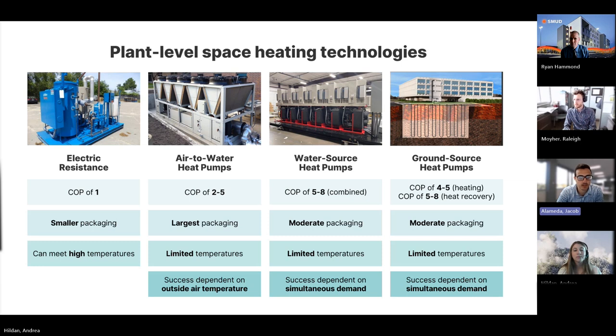The next up on the list are water source heat pumps. These are similar to air source heat pumps, but instead of pulling heat out of the air with the vapor compression cycle, this equipment uses some other water source to pull heat out of. This doesn't necessarily work on every project because you need a water source with enough heat in it to make it work. And your water source can be a lot of different things. Most recently, I've seen projects using campus chilled water return loops as that water source. You pull heat out of the chilled water return to generate your heating water, and then that can actually allow you to provide your building with chilled water as a byproduct on the other side.